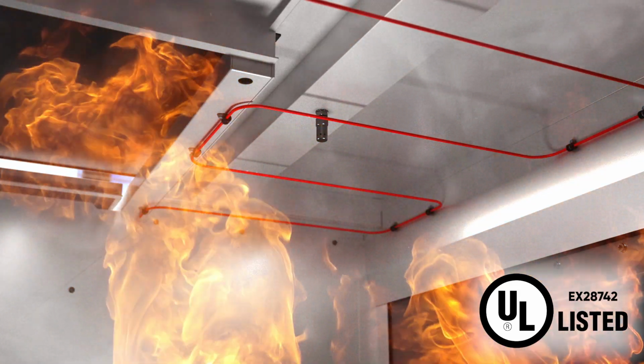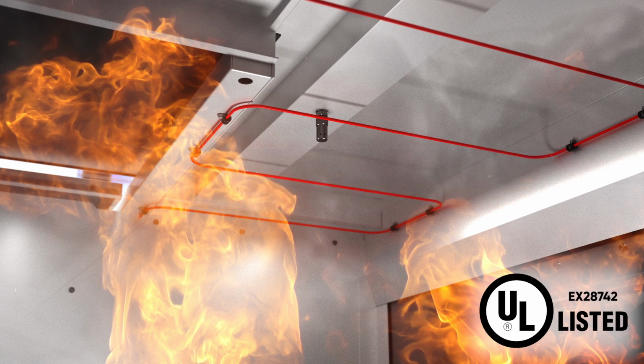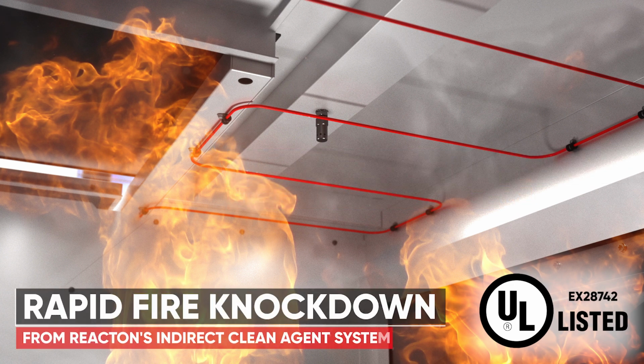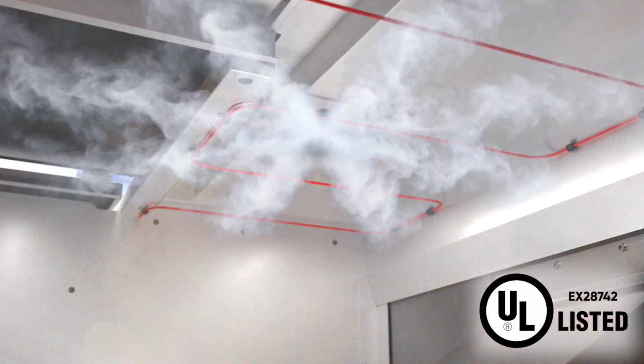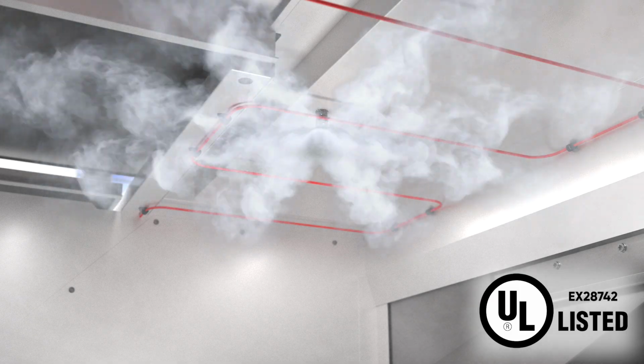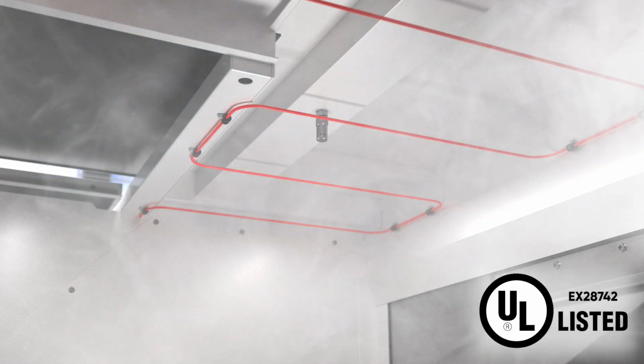The pressurized tubing is installed inside the risk area. The radiant heat from the fire will burst the pneumatic detection tube and activate the fire suppression system, providing fully automatic fire suppression 24/7. Rapid suppression and correct application of the clean agent is taken care of with our dedicated nozzles, allowing for your Class B risks to be quickly combated.